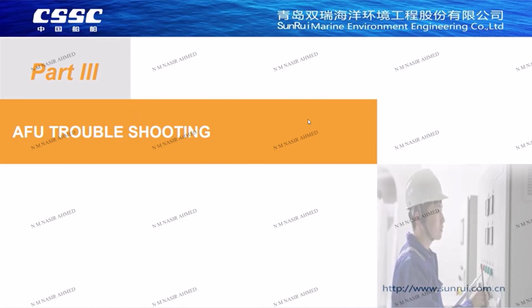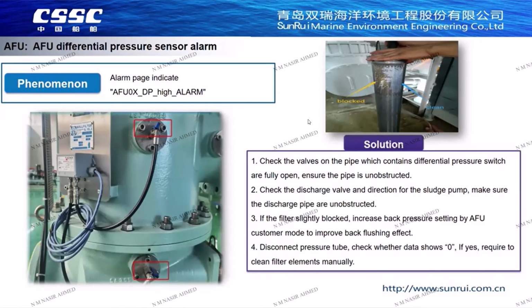The third part is the fault treatment of the filter. The first one is the filter differential pressure high alarm. First, confirm the small blue ball valve on the pressure pipe has been opened. Check whether the sewage pipeline is unobstructed. If it is confirmed the filter is slightly blocked and caused a high DP alarm, you can increase the filter outlet pressure in customer mode and increase the back flushing efficiency to reduce the differential pressure. If it is confirmed that there is no problem with the differential pressure and the automatic back flushing has no effect, the filter needs to be disassembled for cleaning.